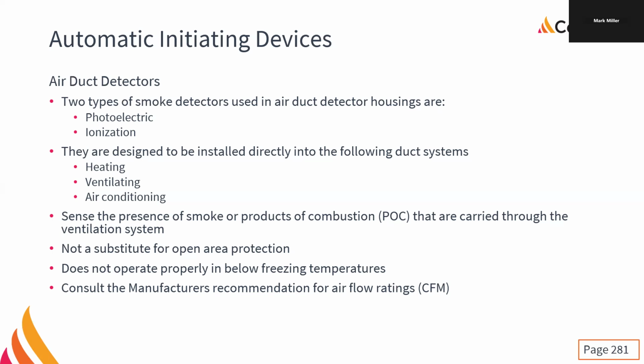They run on 24 volt DC. Run it right off the fire alarm panel, the non-resettable power. It's self-thermostating, so it only turns on when it's cold, and it just keeps the duct smoke detector inside its enclosure from getting cold and damp and failing. The other thing we have to worry about is airflow rating. Some of this ductwork is really, really high airflow, and it can be too windy for them to work properly. So we might have to put in lots of extras.